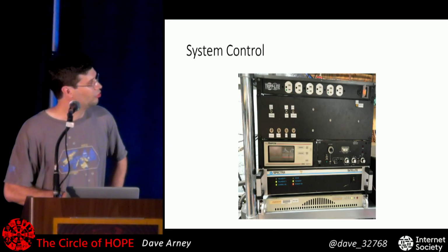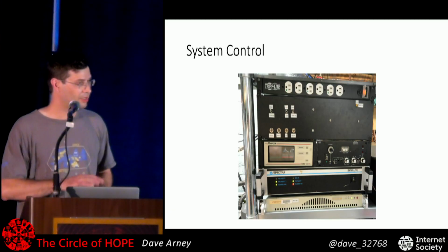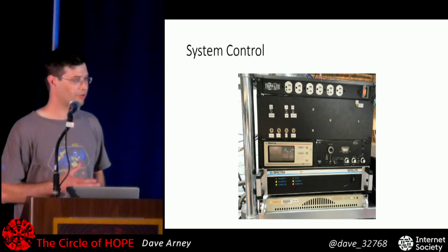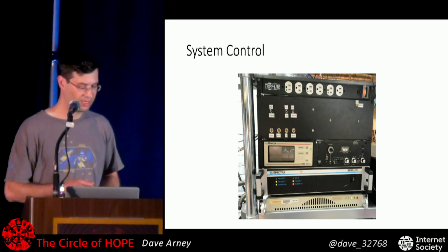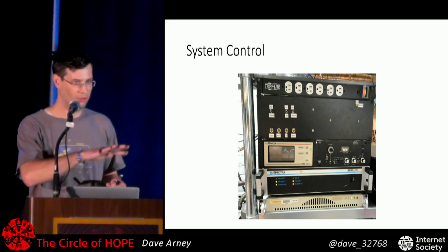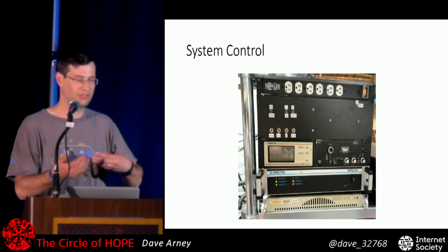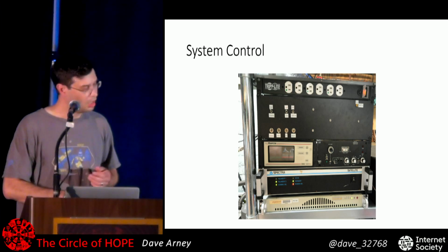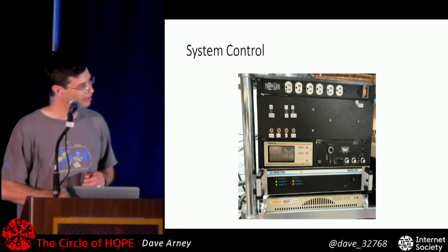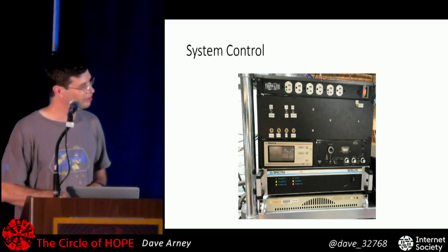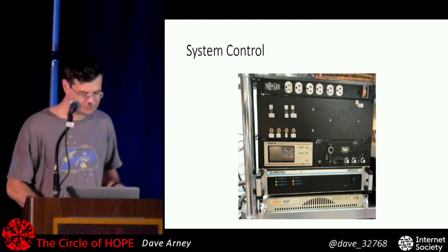So that's that control panel. These are another pressure gauge, and the controller for that conductance valve - this connects to one of the pressure gauges. It has a bunch of settings and a little PID loop controller to control the position of that flapper valve to keep the right pressure in the chamber. The residual gas analyzer, and then the old Pentium - I think it's a Pentium 2 actually - computer that's running Windows 98.